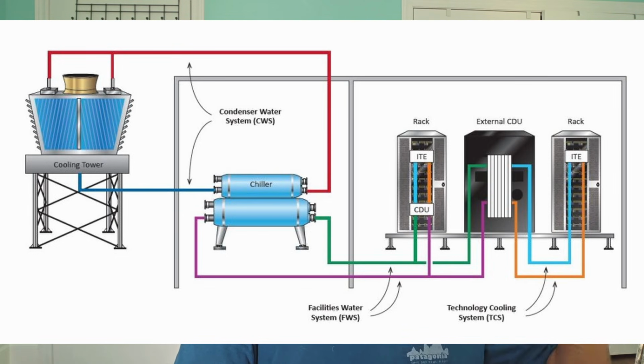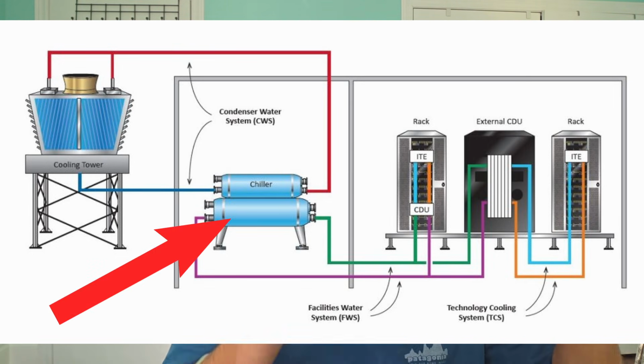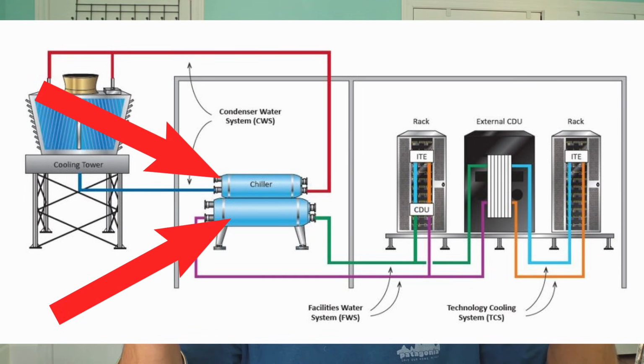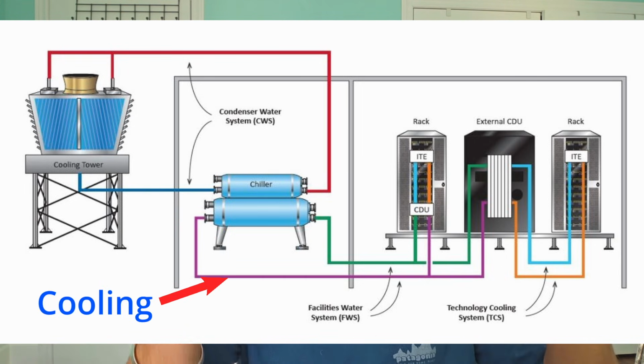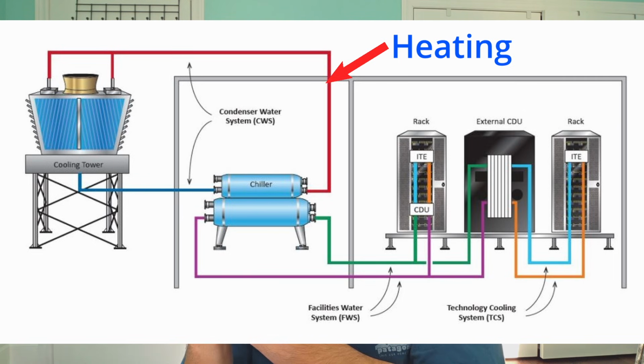So the chilled water that's returning from the building, we call that return chilled water. It's actually now at a higher temperature than what it left at because it collected all the heat from the server racks. So now what we do is take this return water and process it through a piece of equipment called a chiller. As the name suggests, the chiller removes the heat from the chilled water return. That's essentially the evaporator in the refrigeration cycle. And it transfers the heat to the condenser side, right?